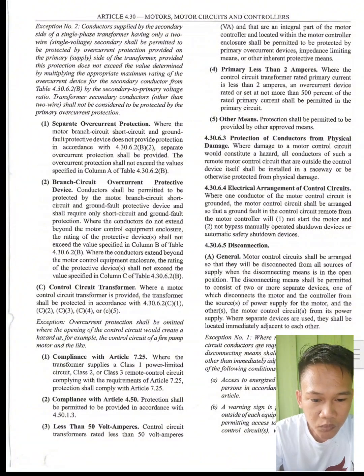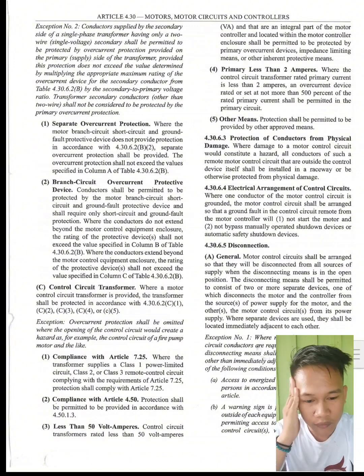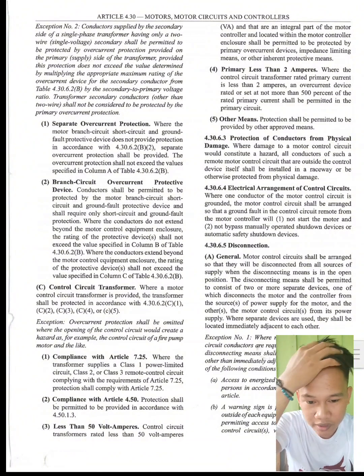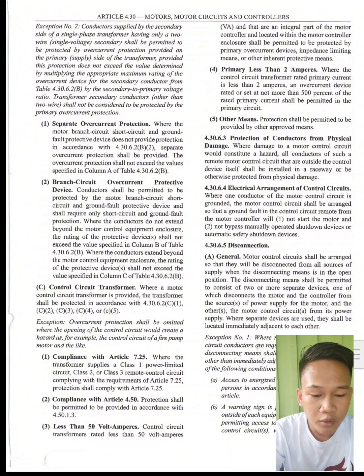So, where the conductors do not extend beyond the motor control equipment enclosure, the rating of the protective device shall not exceed the value specified in column B of table 4.30.6.2b. Where the conductors extend beyond the motor control equipment's enclosure, the rating of the protective device shall not exceed the values specified in column C of table 4.30.6.2b.